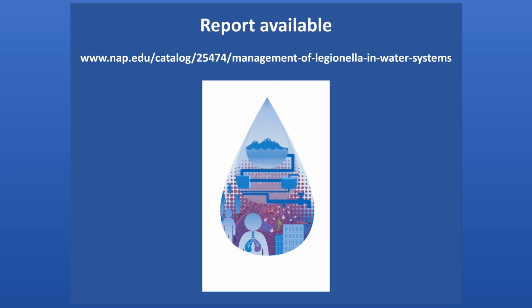Next question: would a recirculating domestic hot water system reduce Legionella bacterial growth potential? It really depends on what temperature you're maintaining the hot water system at. The committee would suggest you need the hot water heater at least 60 degrees C, and at least 55 degrees C in all the recirculation loops and out to the distal points. If those criteria were met, you would have very low, if any, Legionella growth potential.